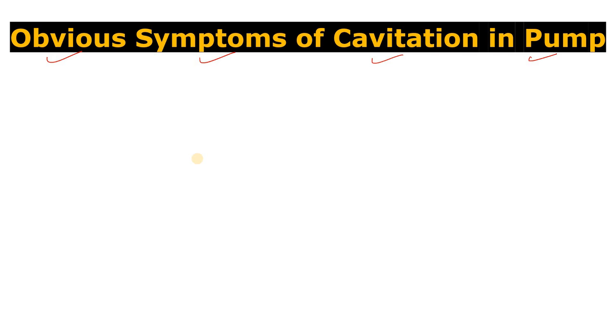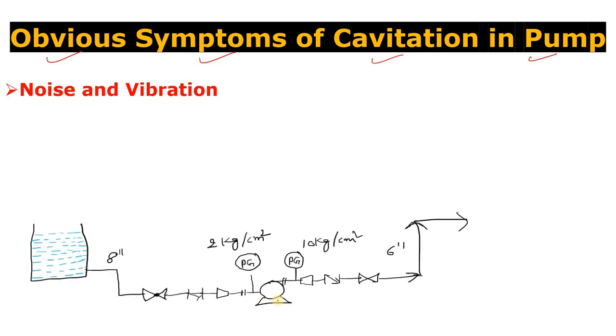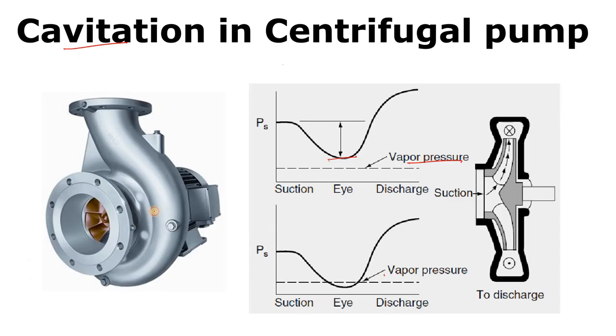The first symptom of cavitation in a centrifugal pump is noise and vibration from the pump. Here you can see this is the centrifugal pump and this is the graph of the cavitation. Cavitation is basically the formation of bubbles and then the collapsing of those bubbles.